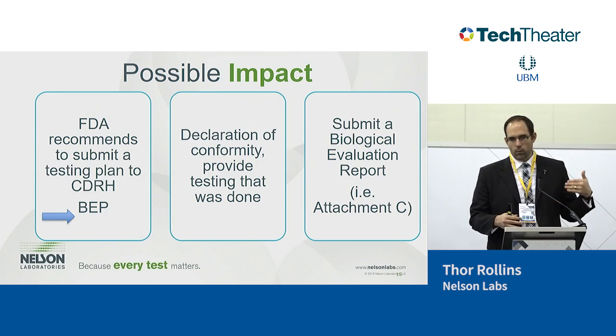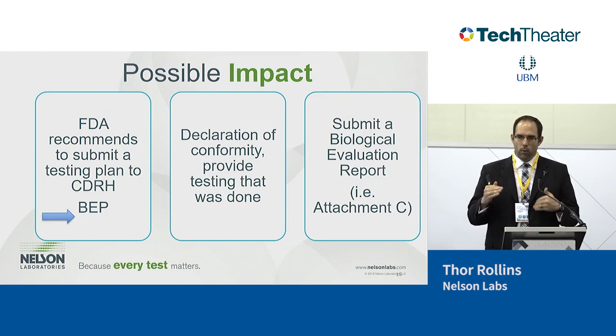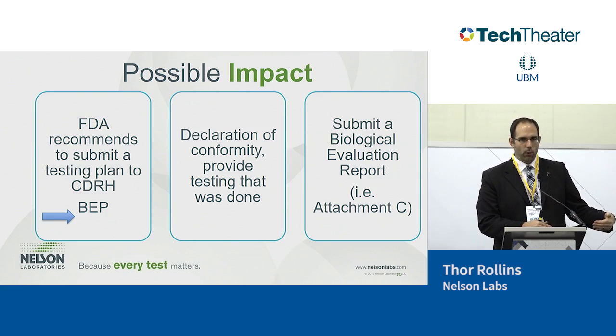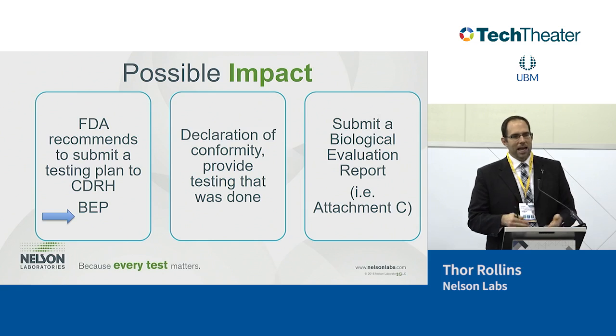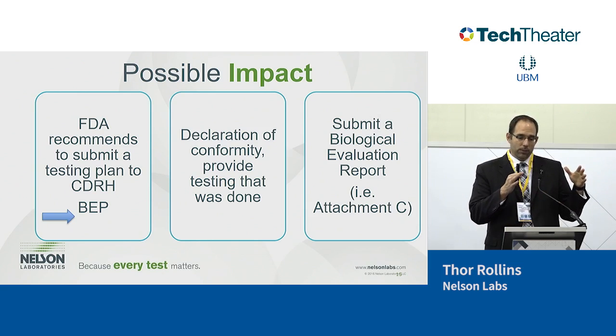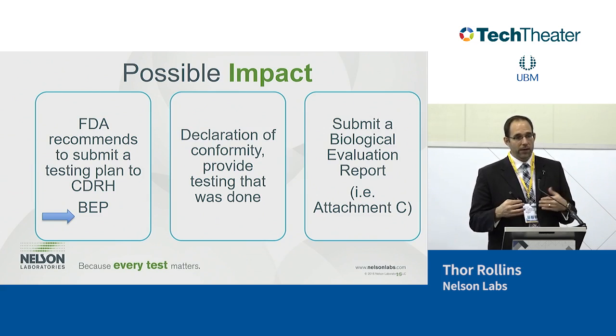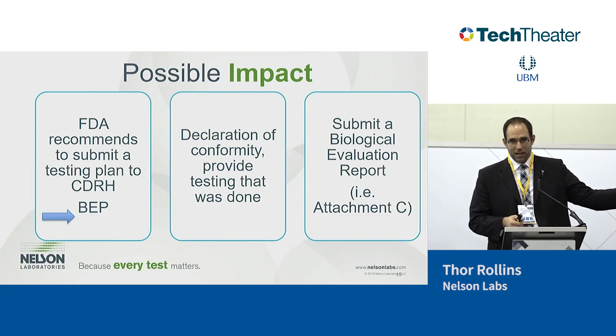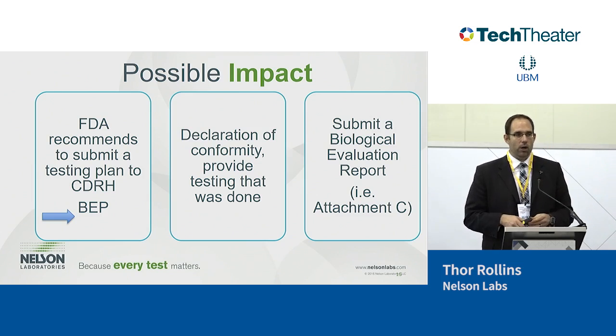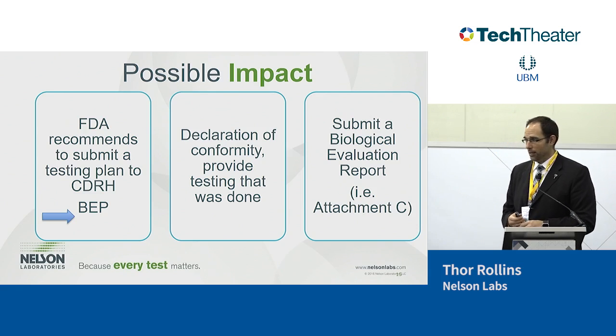So come up with this plan. We call them BEPs, Biological Evaluation Plans. And it spells out what the risk of the device is, what the materials and processes are, what endpoints you need to assess, how you're going to assess those endpoints, and come up with a conclusion. You can submit that in a Q-sub or a pre-sub with the FDA and get really good, helpful feedback. Then you don't have to do unnecessary testing. We can be very selective on how we approach those endpoints in that pre-sub and get real good feedback. And then you know you're not over-testing, or under-testing. You know exactly where you're at. And this has been a very successful process for us when we've been able to do it.